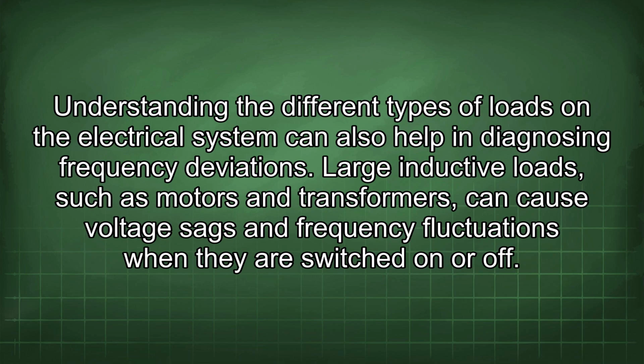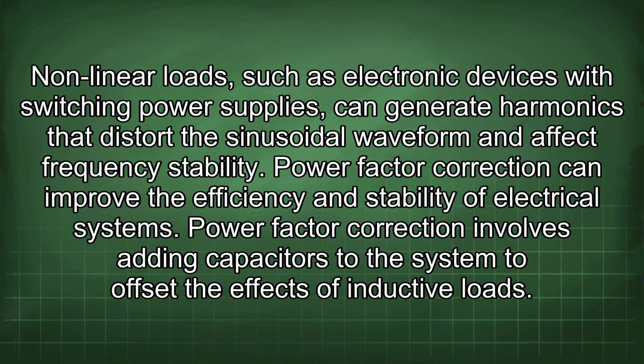Understanding the different types of loads on the electrical system can also help in diagnosing frequency deviations. Large inductive loads, such as motors and transformers, can cause voltage sags and frequency fluctuations when they are switched on or off.